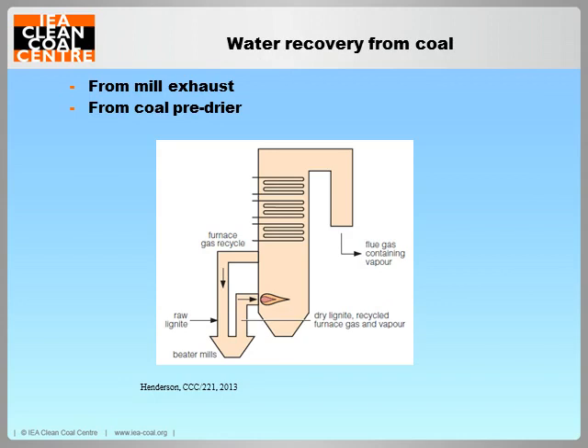Both options would also result in a lower flue gas volume and consequently lower water consumption in wet cooling towers and the wet FGD systems. Moreover, the plant's thermal efficiency would increase. The efficiency could increase by about 1 percentage point when retrofitted to an existing lignite-fired power plant, and by some 4 to 5 percentage points on a new power plant that employs a dry cooling system. Well, these values are on a lower heating value basis.